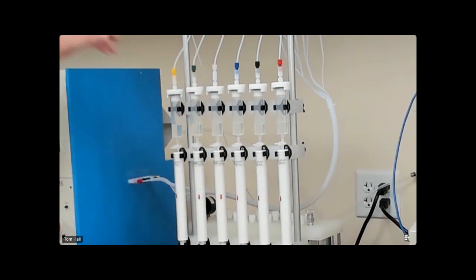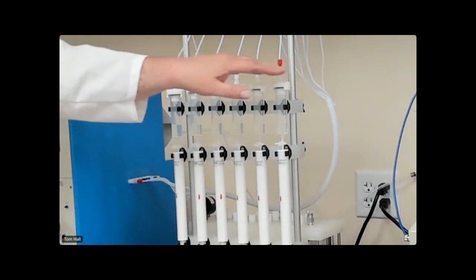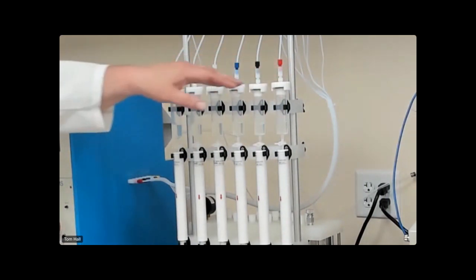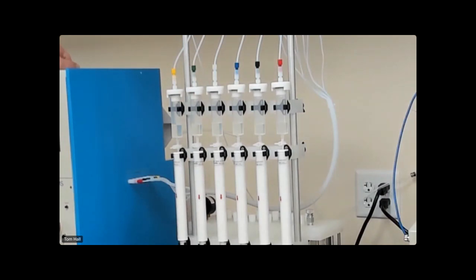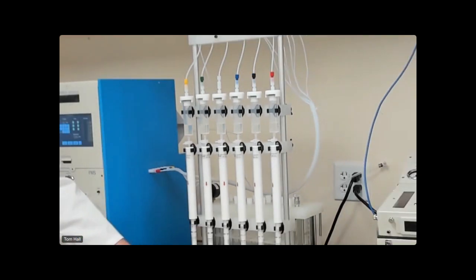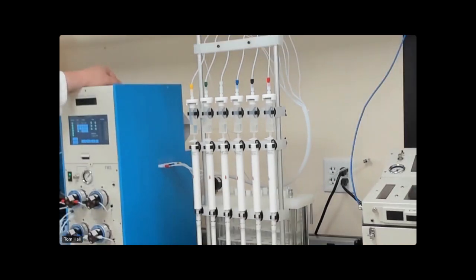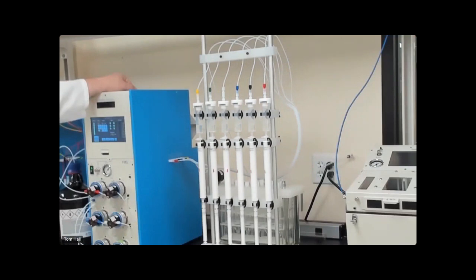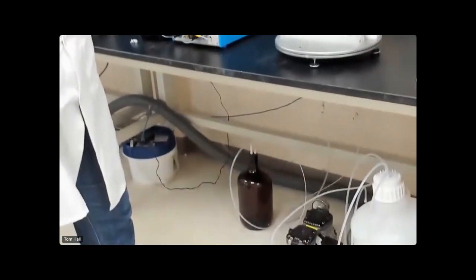There are caps on top here that you can twist 90 degrees with an O-ring on the inside to give a good seal. And these are the color-coded connections of the solvent lines with each of the 6 samples. On the other side, you'll see that later, you can twist this around 180 degrees. There's also a little button here that you can tighten so that it doesn't rotate around inadvertently. So this is the side where everything goes to waste. On the other side, we have a glass manifold, or a fish tank, as we call it, with 12 collection tubes in there. You might be able to see it through the different columns at the back.